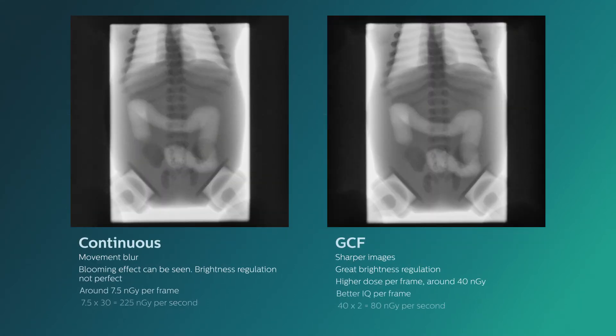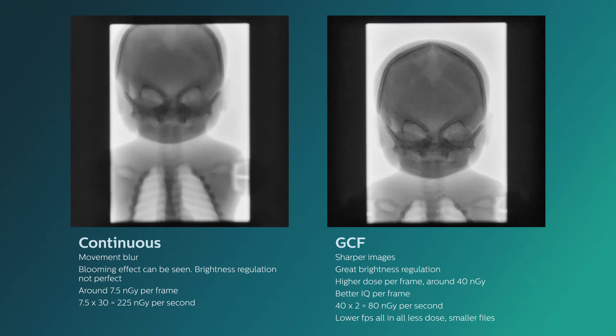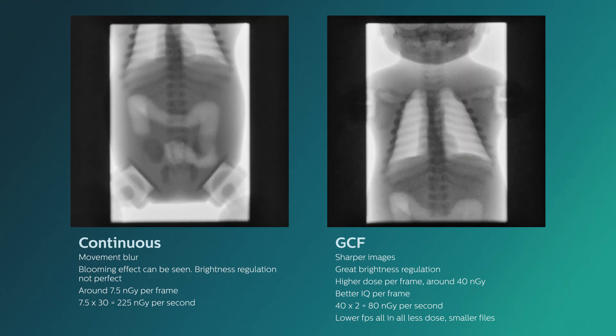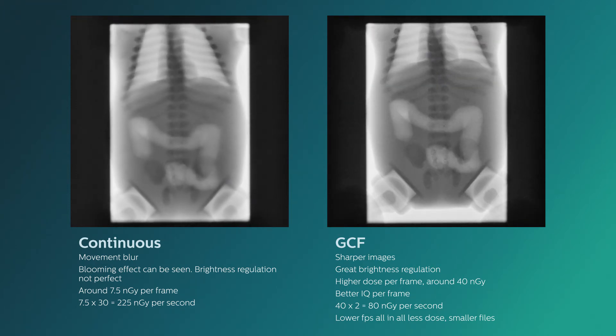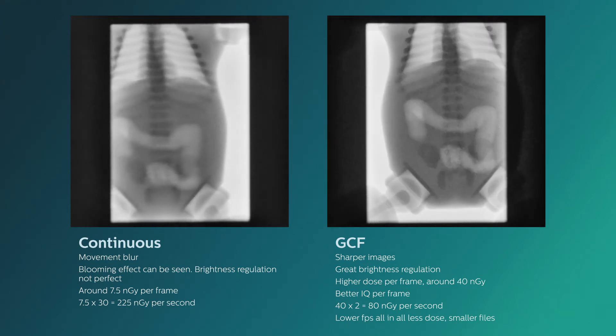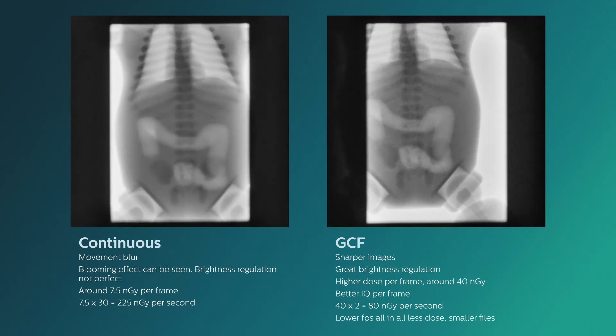Philips does this in conjunction with a patented technology called in-pulse control. In-pulse control optimizes each pulse independently from the very first pulse, modifying the beam kV, mA, and duration to ensure optimized diagnostic quality and the exact dose requirement for each area of the patient anatomy.